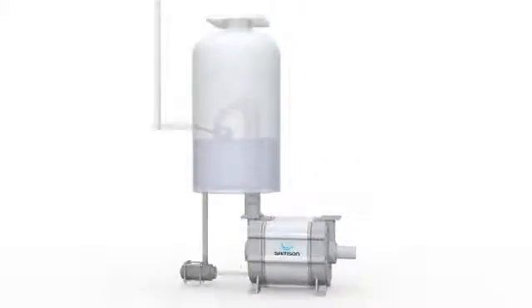To recycle the service liquid, a liquid separator can be mounted on the pressure side of the pump. A liquid separator can reuse about 90% of the service liquid. A float valve connected to a fresh water supply ensures water levels inside the liquid separator are constant.